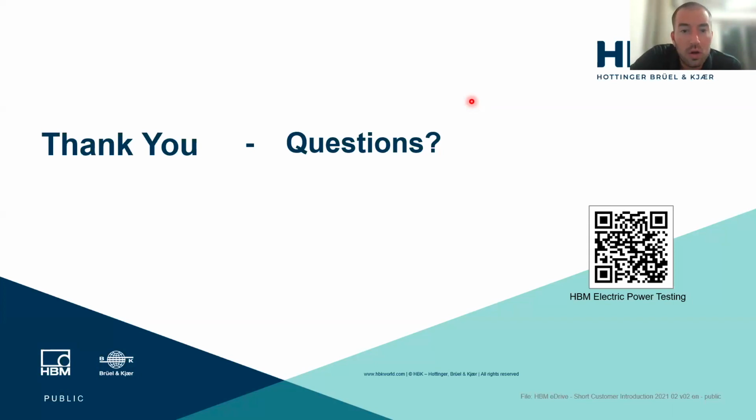All right, let's see. Question presented about the CT box. In the current transducer box, couldn't you just end the shielding in the box itself and not route it for each cable around the CT clamp? That very much depends on the inverter, and thank you, Max, for the question. Completing the shielding loop for the inverter is a lot of times you need that to make it function happily and function in its normal state. And also for the inverter's sake, you want to complete that shielding loop.